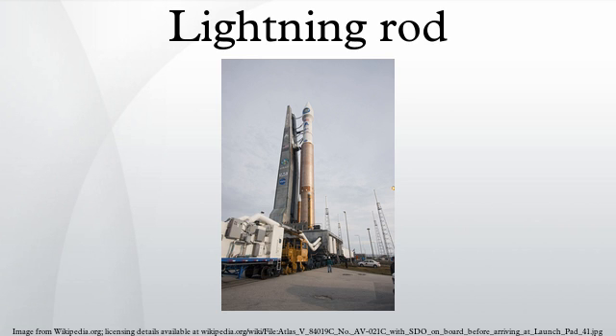Lightning conductors and grounding precautions. Ideally, the underground part of the assembly should reside in an area of high ground conductivity. If the underground cable is able to resist corrosion well, it can be covered in salt to improve its electrical connection with the ground. While the electrical resistance of the lightning conductor between the air terminal and the earth is of significant concern, the inductive reactance of the conductor could be more important. For this reason, the down conductor route is kept short, and any curves have a large radius.